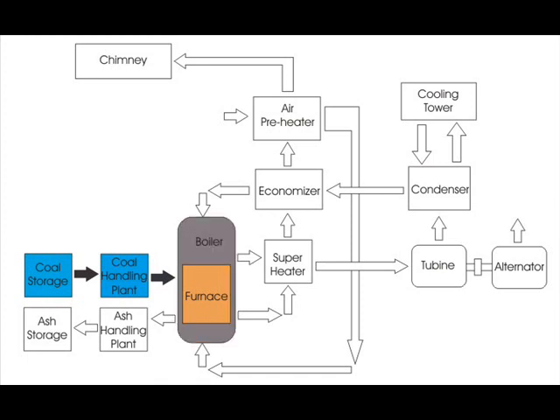Now, come to the steam generating plant. The heat produced in the furnace is utilized to convert water into steam in boiler. The flue gases from furnace make their journey through superheater, economizer, air preheater, and they are finally exhausted to atmosphere through chimney. The steam produced in the boiler is not fully dried. That is why it has to pass through a superheater, where the steam becomes fully dry and superheated much above the boiling temperature of water by the flue gases on their way to chimney.